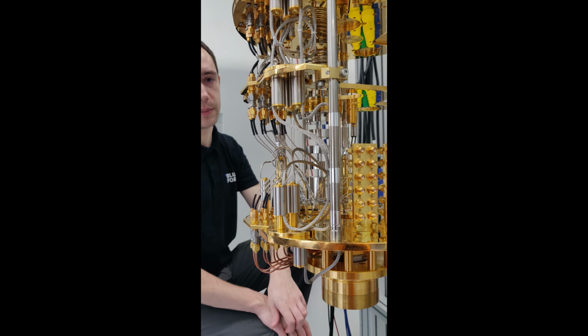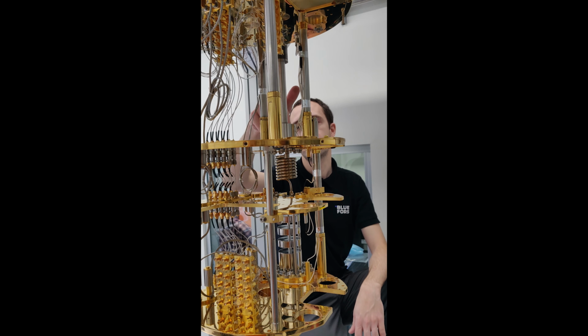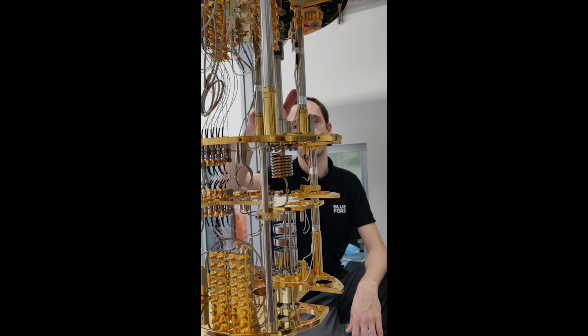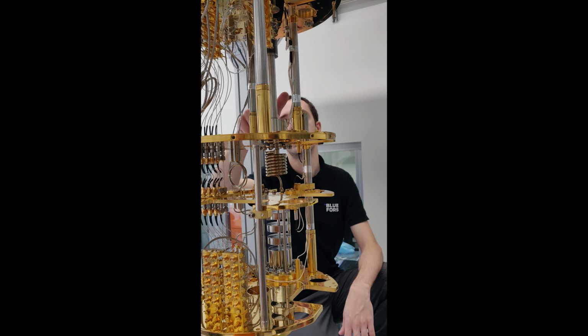So even if there are leaks inside this thing, for example, there are soldering points, there is some, I don't know, some glue or something, they all stay inside steel, so they don't leak out into the cryostat volume. You don't lose mixture. Of course, you may lose the cooling power, but that's how you see that it's not a good unit. But at least you will not lose the mixture. Right, then the helium-3 goes down, and at the lowest point at the still, there is the main flow impedance, and there, due to the Joule-Thomson effect, it finally condenses, if it was not liquid before that.